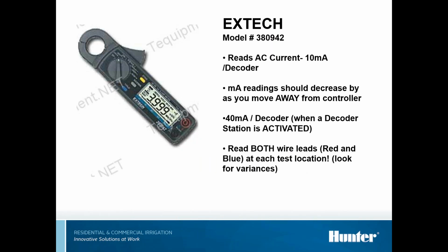Extech reads AC current, and it says 10 milliamps per decoder, so that's about right. A little bit more, a little bit less is not going to be catastrophic, but you can tell if it's way low or way high, you've got something going on. Your milliamps reading should decrease as you move away from the controller if you're doing the 2-wire path, because you're dropping some out the further out you go.